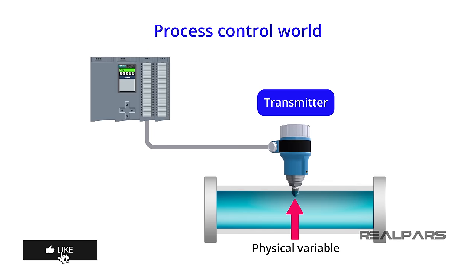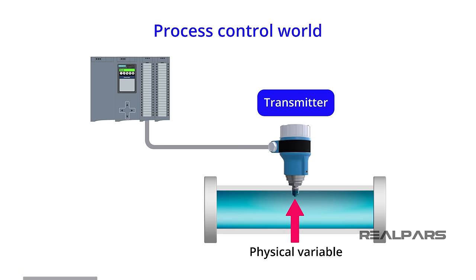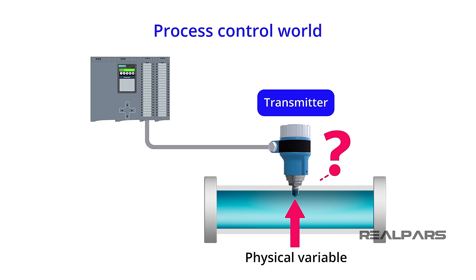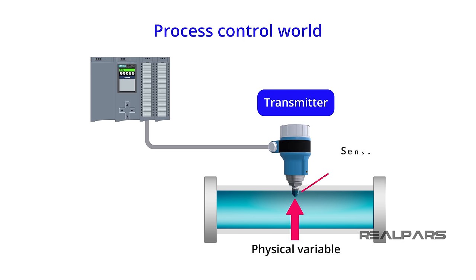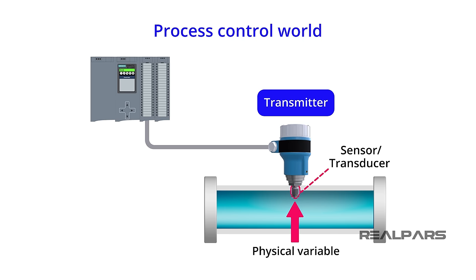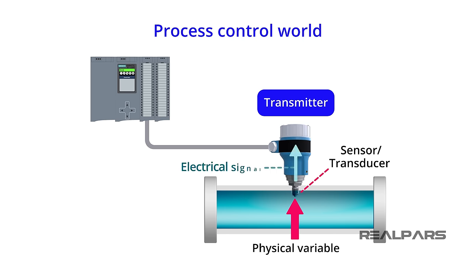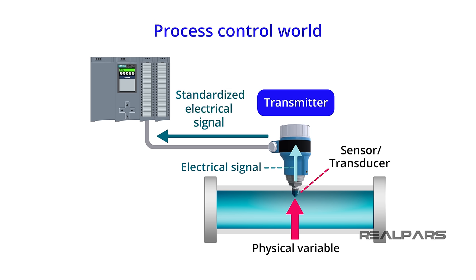So, we just said that the Transmitter signal represents the physical variable. How does the Transmitter know what the physical variable is? That's where a Sensor or a Transducer comes into the picture. A Sensor performs the initial measurement. If necessary, a Transducer converts this initial measurement into an electrical signal that is then amplified and standardized by the Transmitter.